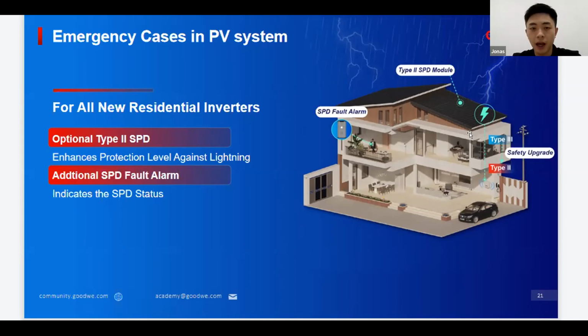Starting from last year, we upgraded the SPD level for all the residential inverters. We added the type 2 SPD option. Another function that we added to the inverter is the SPD fault alarm. That means you can monitor the status of the SPD remotely. If lightning hits the SPD and it is damaged, there will be an alarm, and you can choose to change the inverter or change the built-in SPD board inside the inverter.